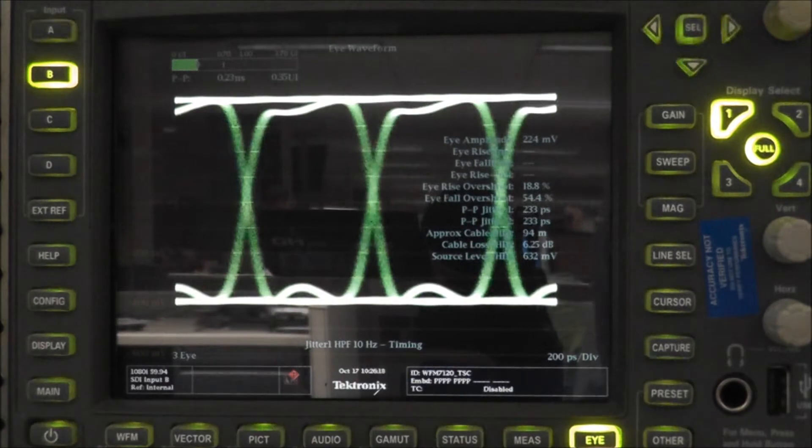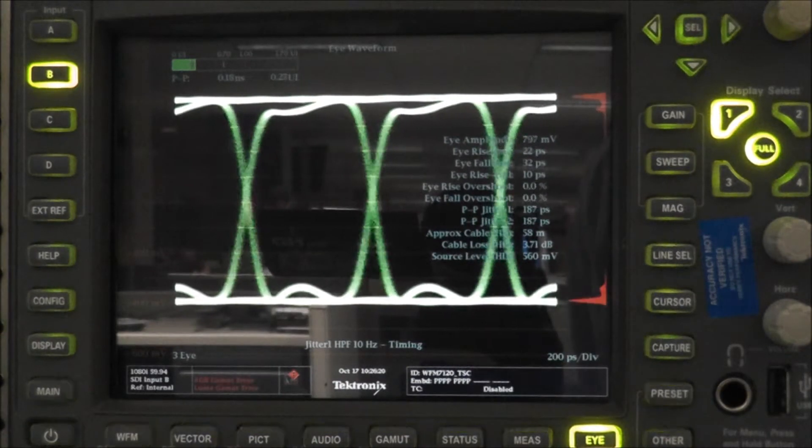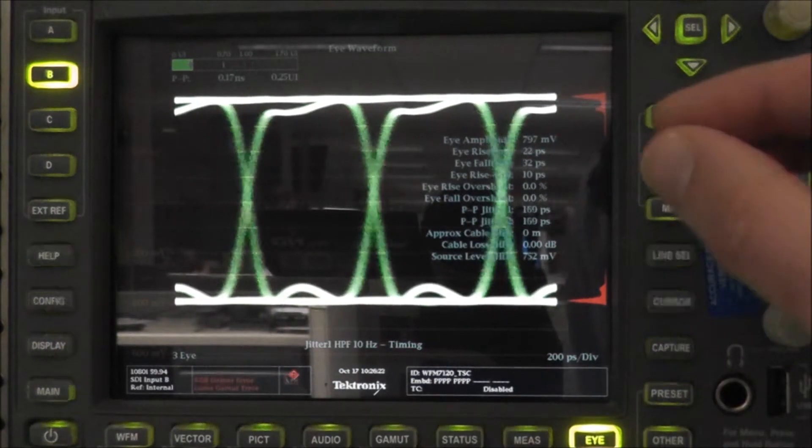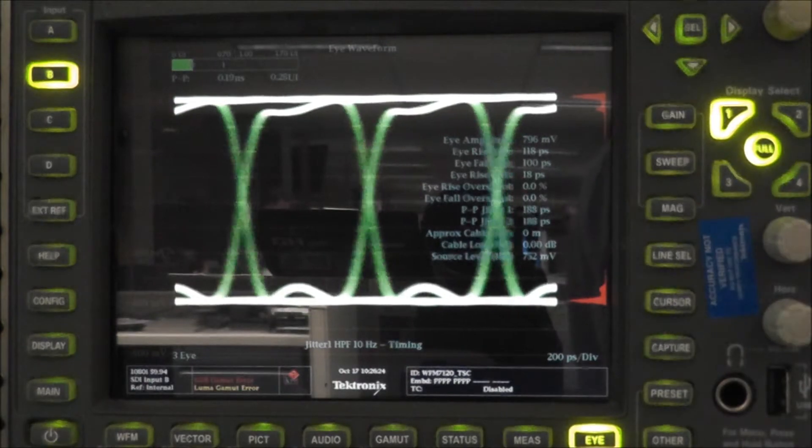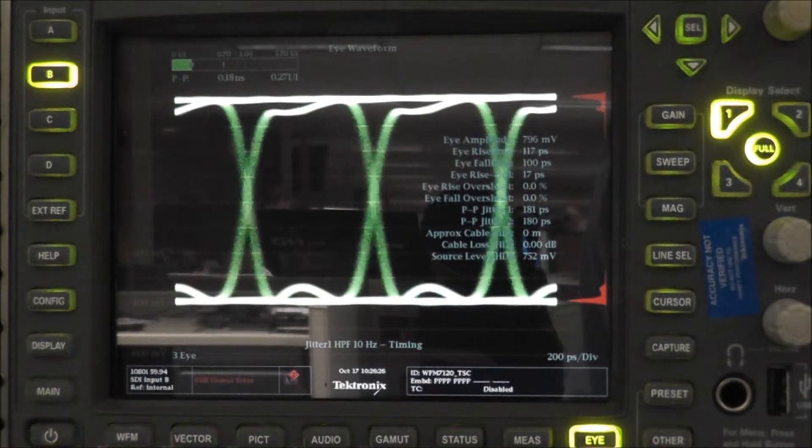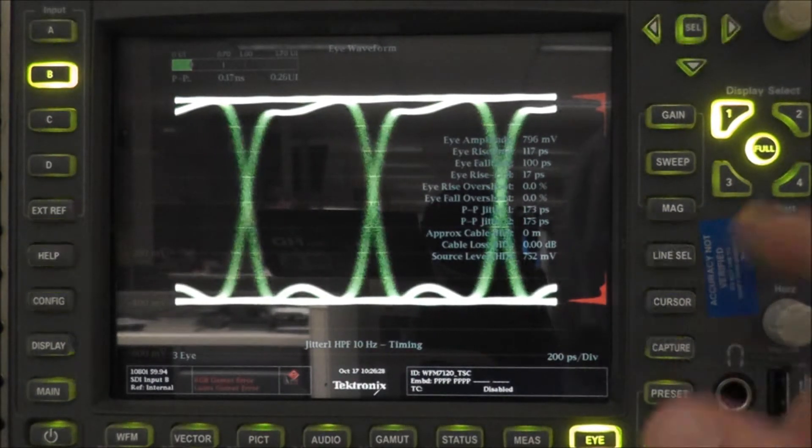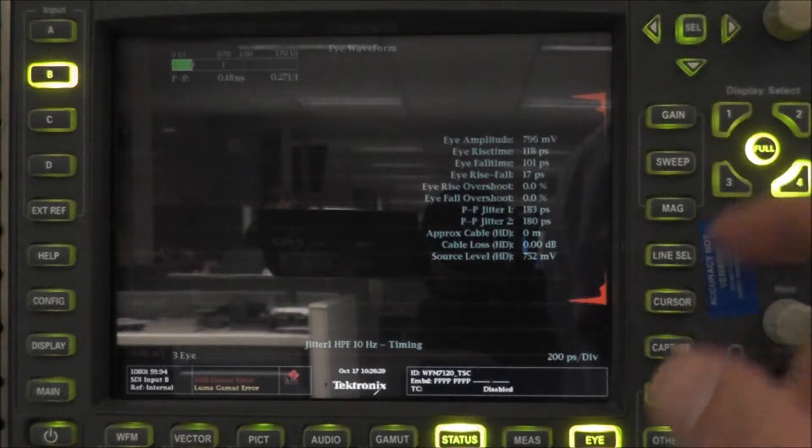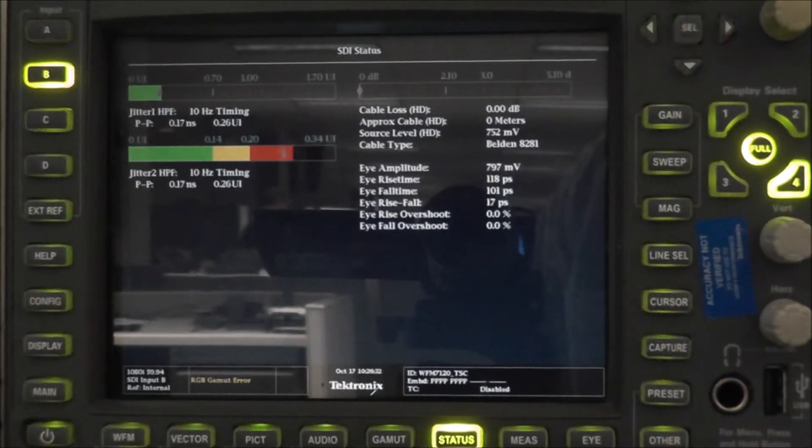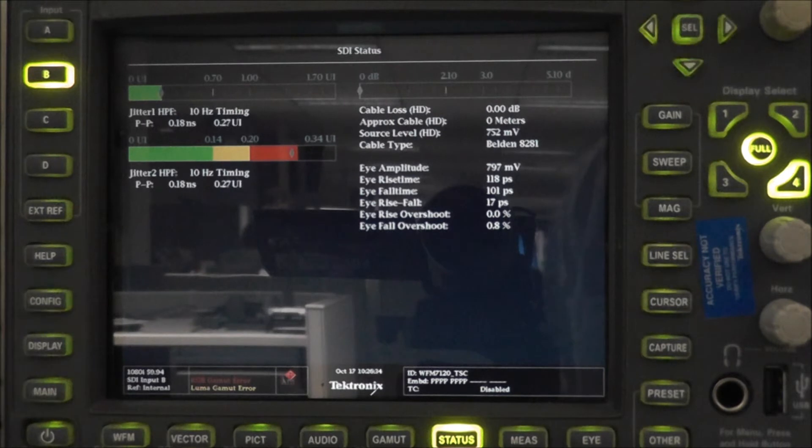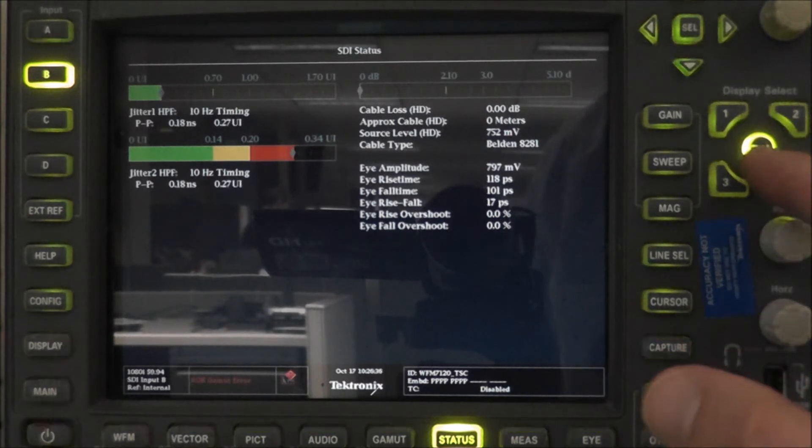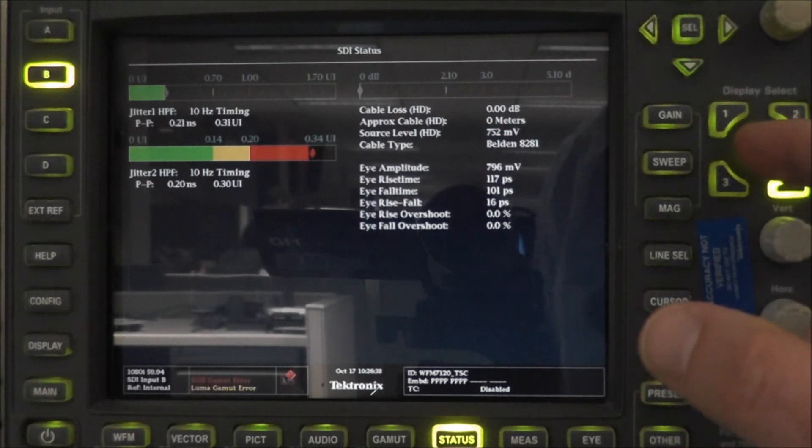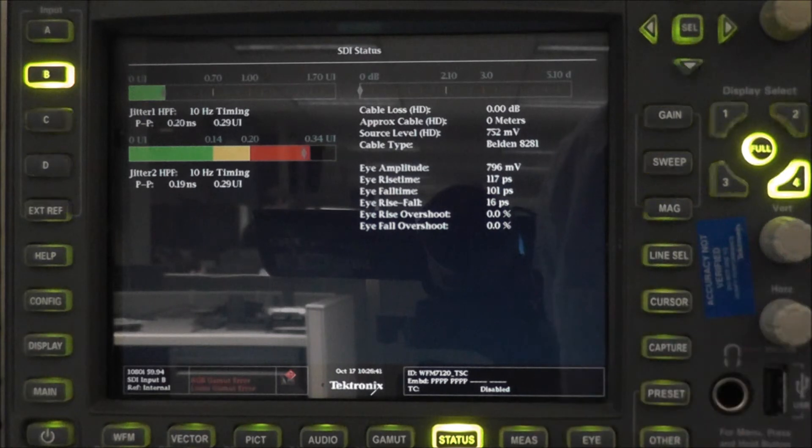I do have this signal being reclocked and passed on over to our second input. At this point, we do see a much cleaner eye. The unit is able to calculate those rise-fall times. You can see here in the SDI status, showing zero meters, and it also shows those eye rise-fall time measurements.